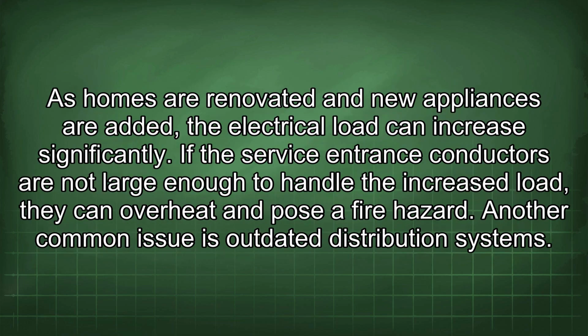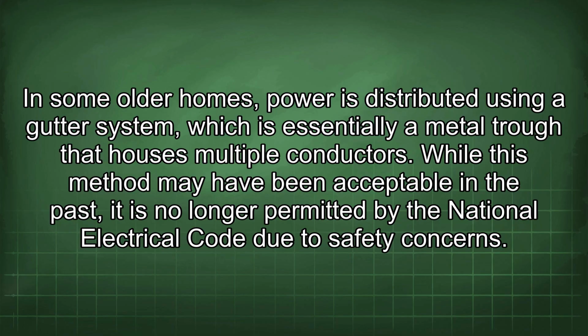As homes are renovated and new appliances are added, the electrical load can increase significantly. If the service entrance conductors are not large enough to handle the increased load, they can overheat and pose a fire hazard. Another common issue is outdated distribution systems. In some older homes, power is distributed using a gutter system, which is essentially a metal trough that houses multiple conductors. While this method may have been acceptable in the past, it is no longer permitted by the National Electrical Code due to safety concerns.